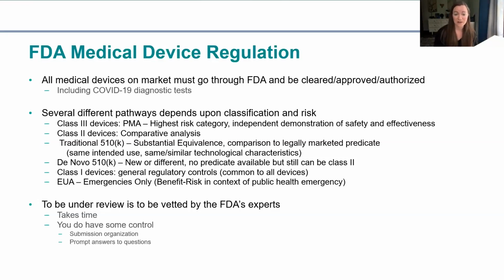Class 3 devices are the highest risk category of devices and require explicit pre-market approval. A PMA submission presents FDA with an independent demonstration that the device is reasonably safe and effective, including its manufacturing and the sponsor's quality management system. Class 3 devices have a heightened regulatory control throughout their total life cycle. For example, design and manufacturing changes can even require FDA approval.